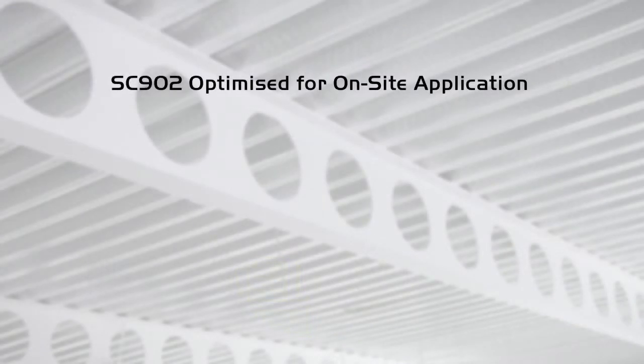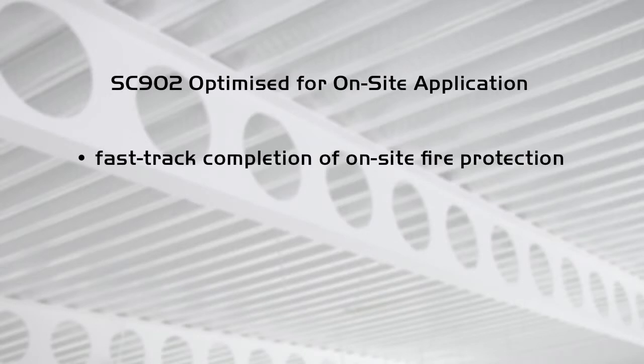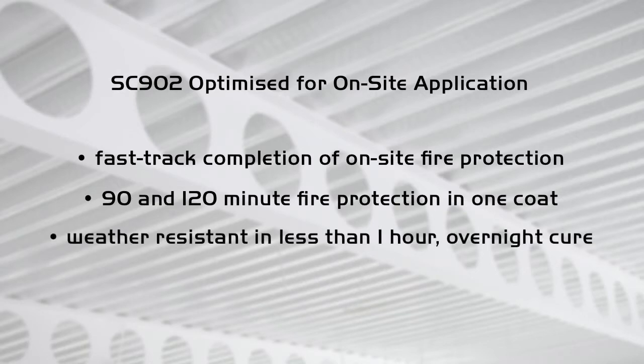SC902 is optimised for on-site application. It provides rapid completion of on-site fire protection, giving a 90 or 120 minute fire protection in 1 coat and is weather resistant in less than 1 hour and is fully cured overnight.